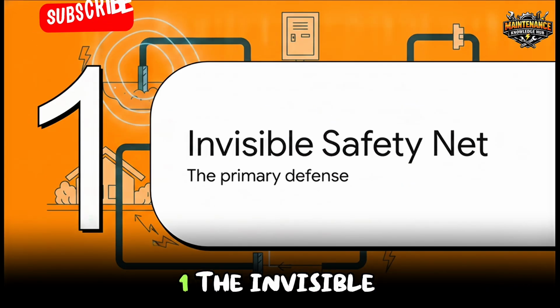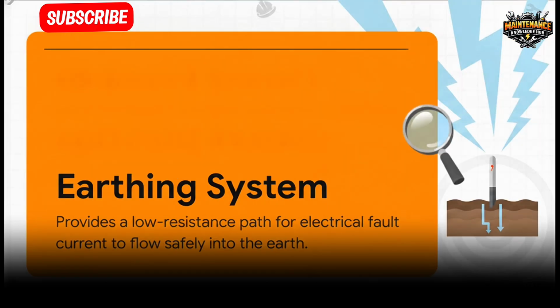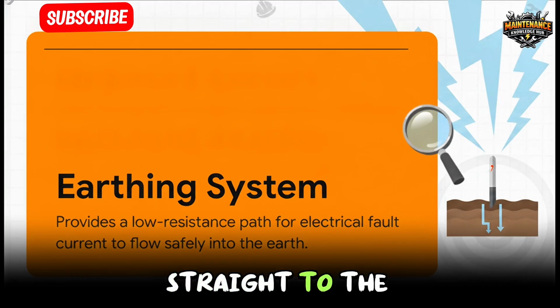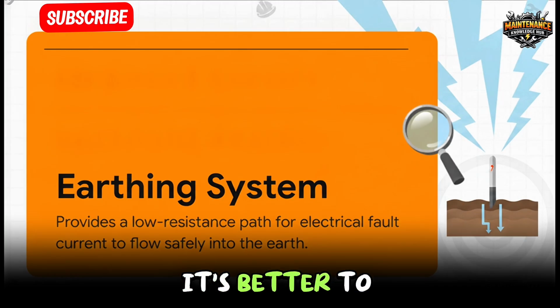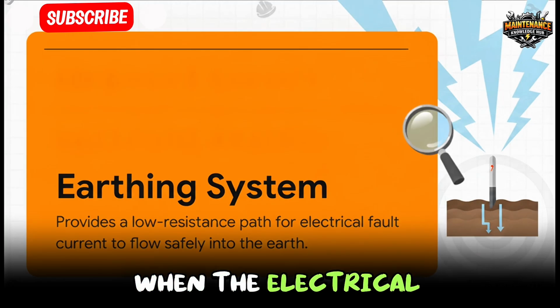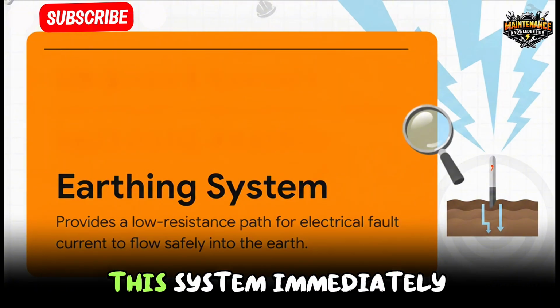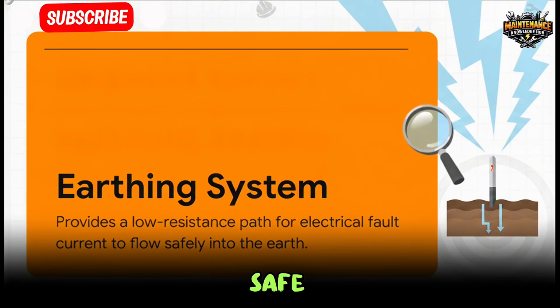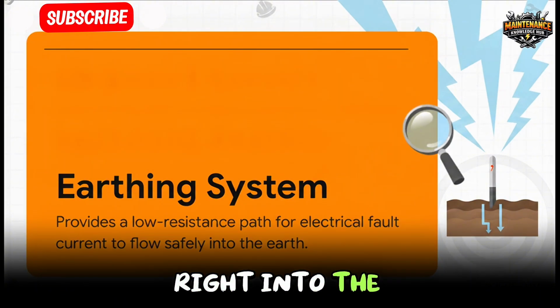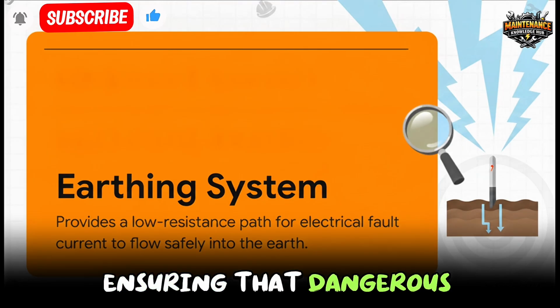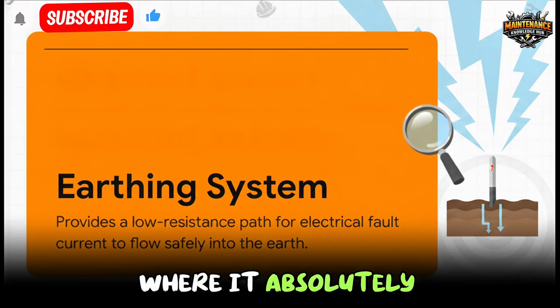Starting with Section 1, the invisible safety net. You probably already know the basics here. An earthing system is simply that dedicated, low-resistance path straight to the ground. But honestly, it's better to think of it less like a simple wire and way more like a high-capacity pressure relief valve. When the electrical pressure dangerously spikes, this system immediately opens up a safe, highly conductive highway right into the dirt, basically ensuring that dangerous current doesn't build up where it absolutely shouldn't.